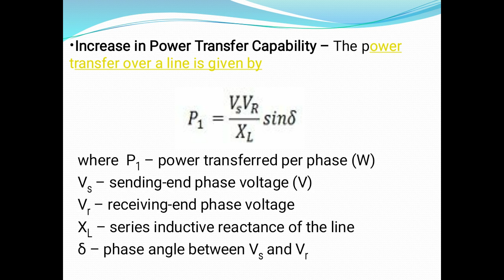Now if a capacitor having capacitive reactance Xc is connected in series with the line, then the reactance of the line is reduced from XL to XL minus Xc. So the power transfer is given by P2 = VS VR / (XL − Xc) × sin δ. Before compensation the reactance of the transmission line was XL, but when a series capacitor is connected, the reactance of the line decreases to XL − Xc, due to which power transferred by the line increases.